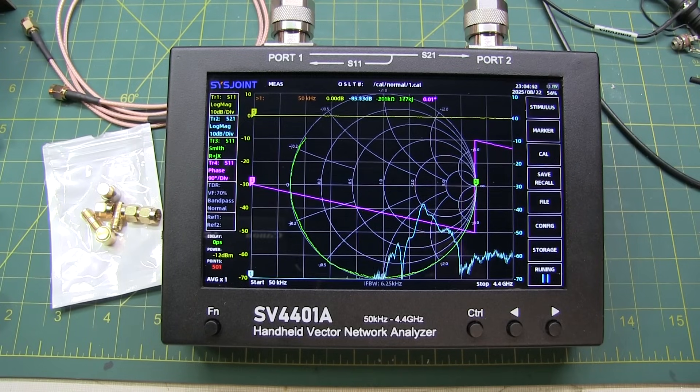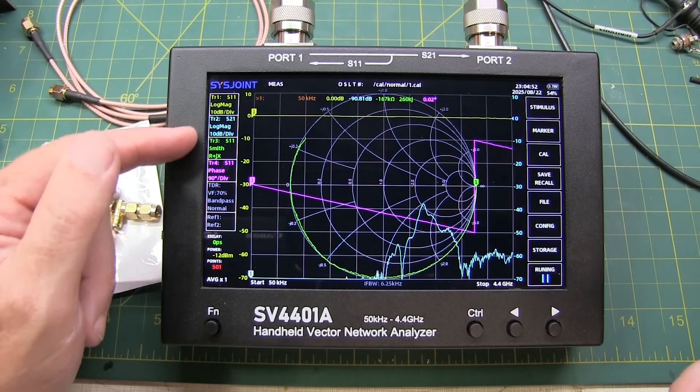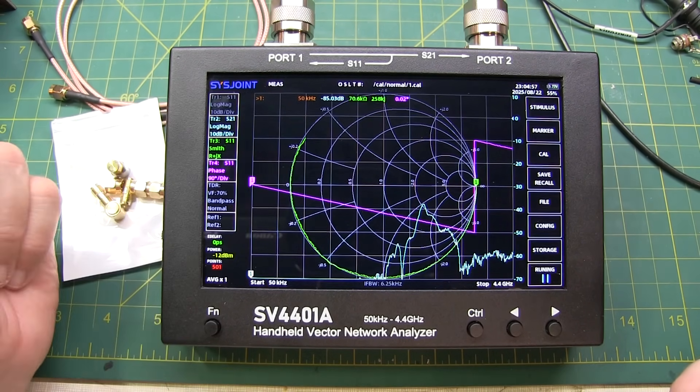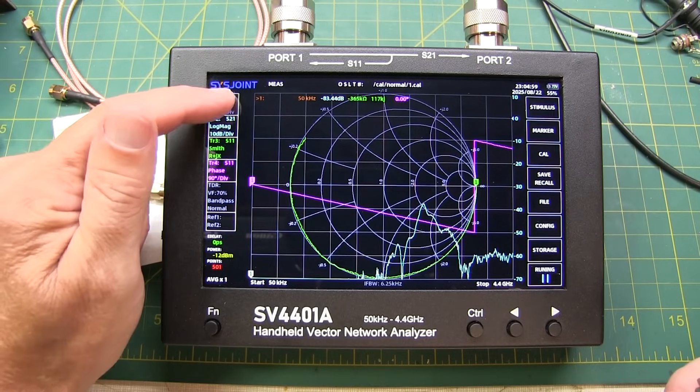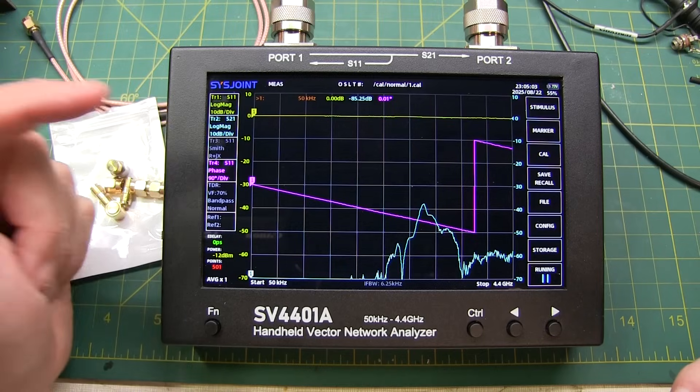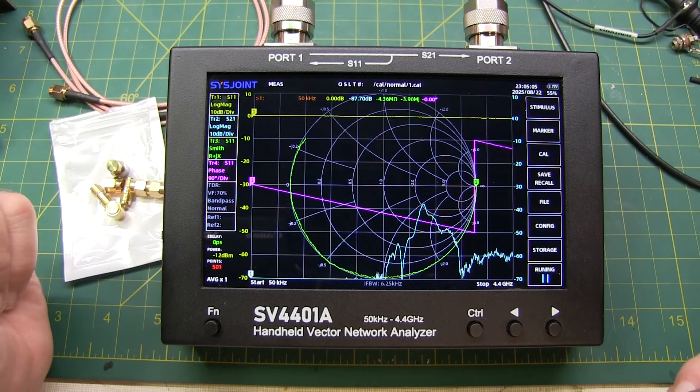For example, the traces are all on the menu on the left hand side here. And simply touching one of the trace badges makes that trace go away. Touching it again brings it back on. If I touch the Smith chart one, the Smith chart goes away. Touching it again comes back on.